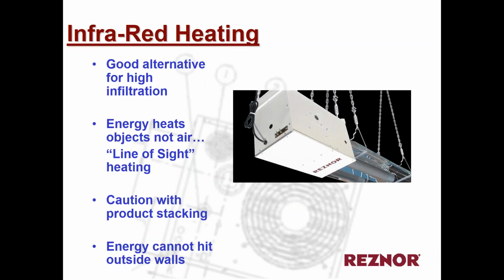We also offer infrared heating, and that's high intensity as well as what you see here, which is low intensity, tubular type infrared heating. This is line of sight heating, meaning that the heater has to have a target in sight to do proper heating. It heats objects and not air like the indirect fired products we've talked about thus far. But it is a great alternative for areas where you have very high infiltration or exfiltration. Places where they may work on vehicles where the doors are opening and closing quite frequently, or they're open all the time. Loading dock areas. They provide warm, comfortable heating in those applications.